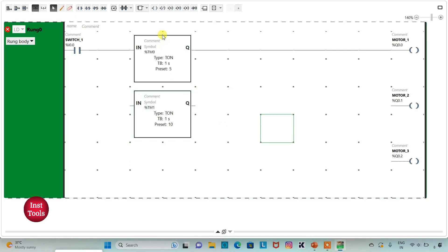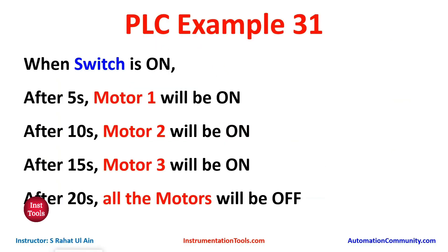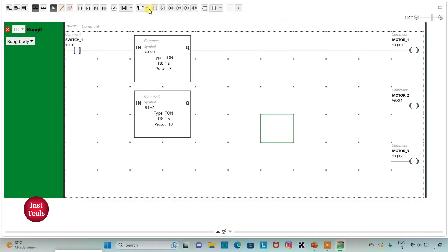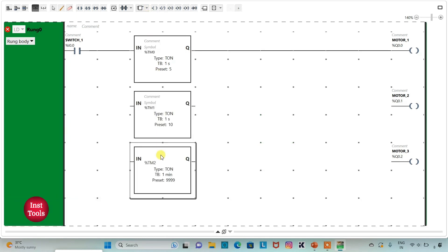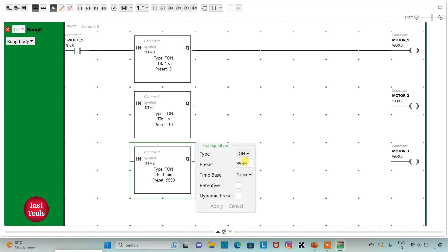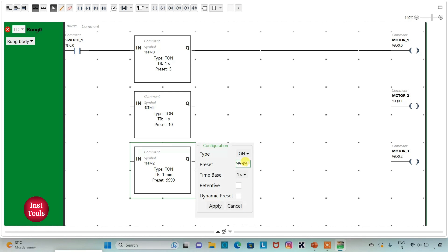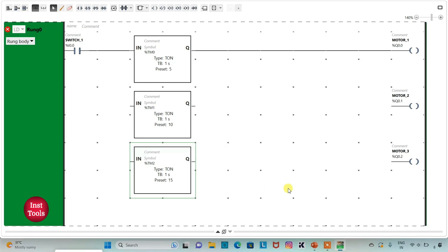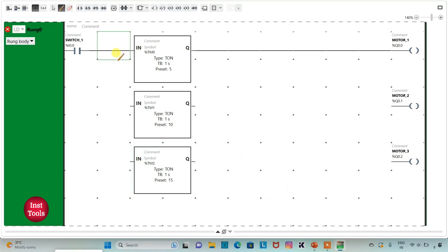And then for motor 3 — motor 3 will be on after 15 seconds. So I will insert another timer for motor 3 using T-ON, change time base to 1 second, and preset it as 15 seconds. Then click on apply. Then I will click on this option and connect it like this.